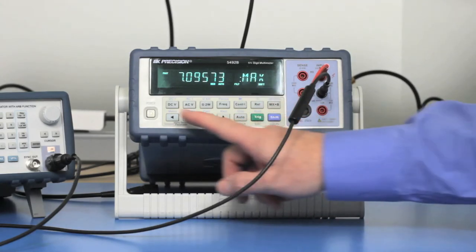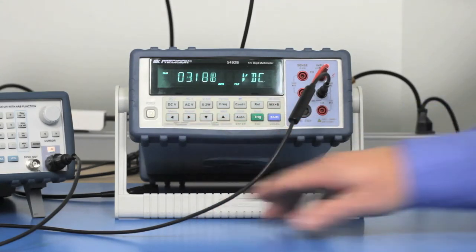To exit this, we do Shift and left arrow, and we're back to doing our normal measurements. So now the data stored into the buffer is in volatile memory, so if you were to power cycle the 5492B, you will lose all of that data, so please remember that.